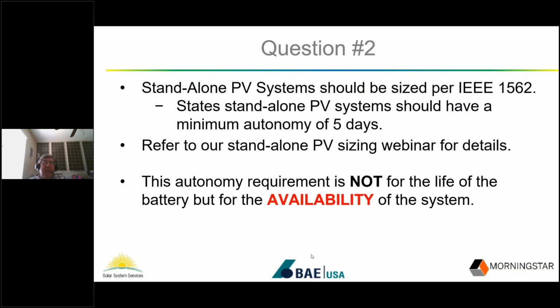When you talk about solar applications, there's a rule of thumb out there - actually not really a rule of thumb. There's a design guide by IEEE, IEEE 1562, and that design guide states that you should have a minimum of 5 days of autonomy for a standalone PV system.